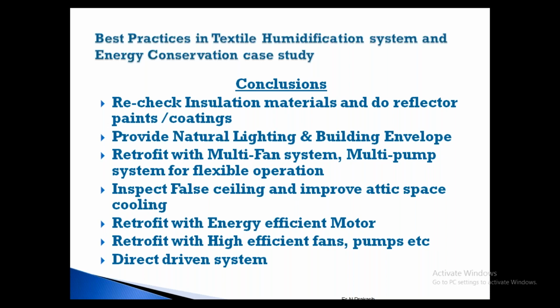Then retrofit a multi-fan system. If you have a single fan of 30 HP or 40 HP, if you are able to change it, retrofitting a multi-fan system will be better, because you have flexibility in operation. In the same way, as I told you about the multi-pump system, you have flexible operation. With a single pump you achieve the RH, and only at peak time you switch on the next pump, so that much power is saved. Otherwise, with a single pump, you will just be throttling the valves.